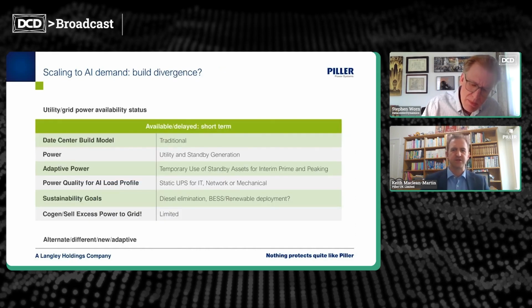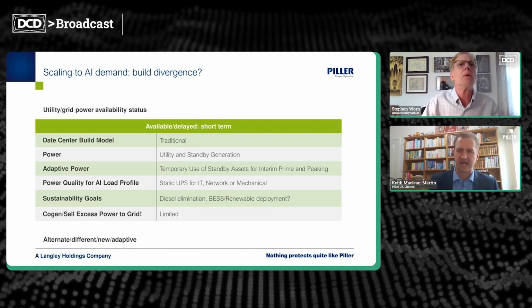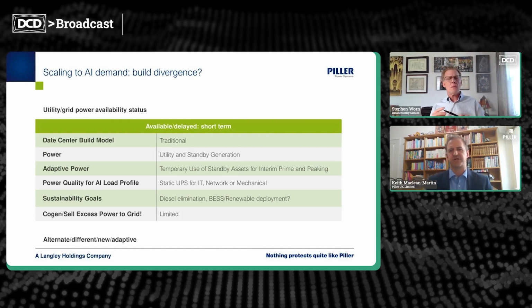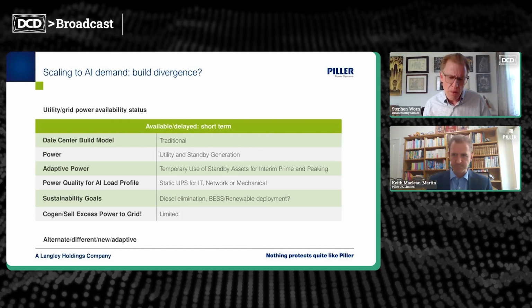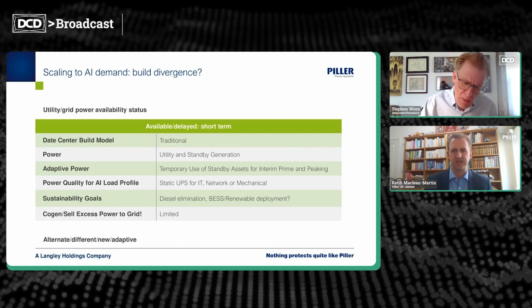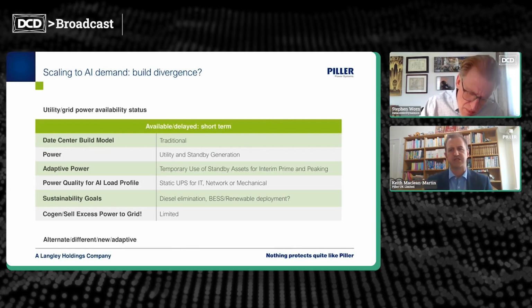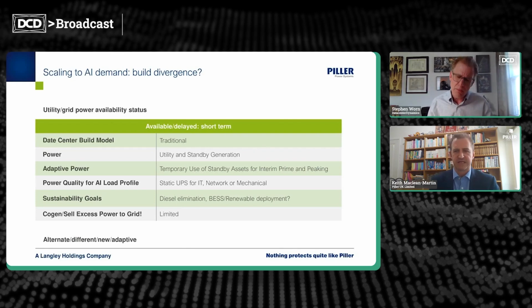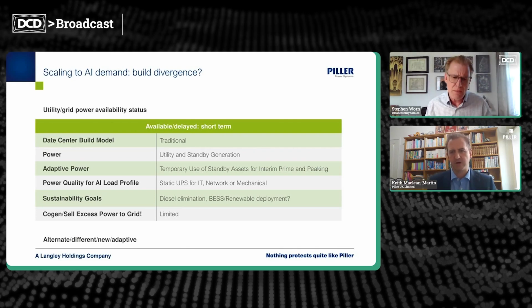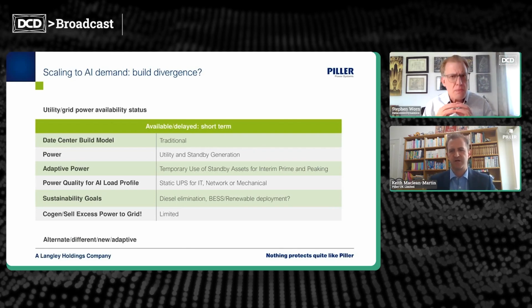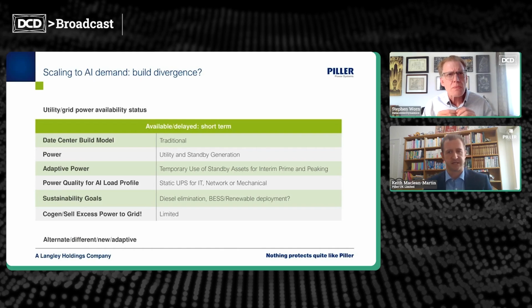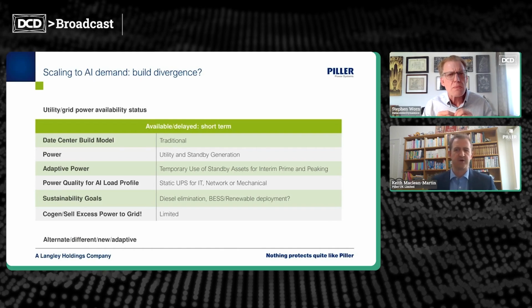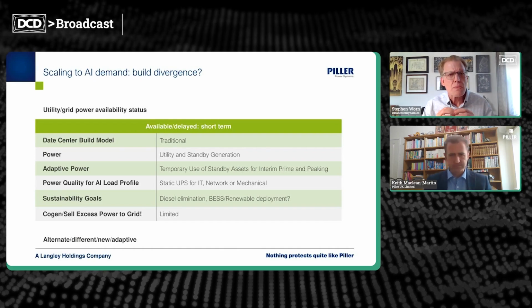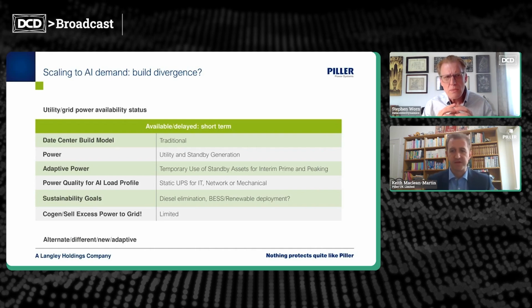So when the grid's not available or delayed by a decade or so, this is where new build methods or strategies are causing divergence. So the removal of standby backup generation and moving to the microgrid on-site generation for prime power capabilities. So prime on-site generation will provide localized baseload power for the data center, day one operating in island mode perhaps, and in the future, possibly with a hybrid with the grid if the connection ever comes to fruition.